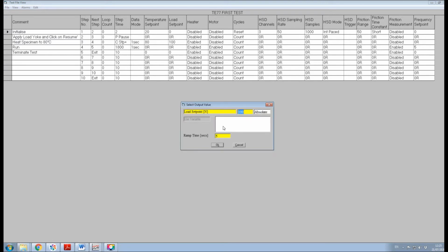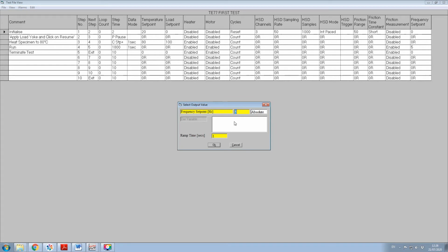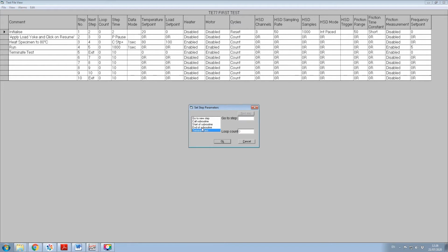In this example, a load has been applied during step 3 and the motor enabled during step 4 with a frequency set point of 5 Hz. This step lasts for 1800 seconds, followed by step 5, which includes the exit statement as the next step. This defines the end of the program and closes the test.